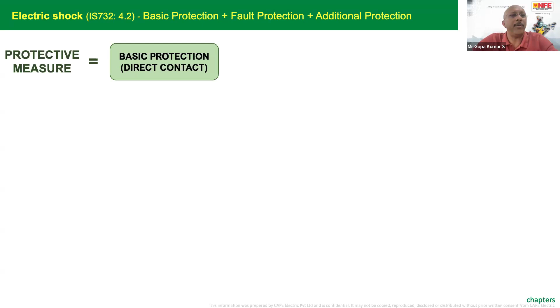If somebody claims that I have a product tested as per IS 732, I request the participants to be alert and careful, and immediately decide that this is wrong, because a product cannot be certified as per the requirements of IS 732. Clause 4.2 of IS 732 explains protection from electric shock, which consists of basic protection, meaning different protective measures which can be applied in an installation so that human beings or living beings do not come in touch with electricity. For example, insulation of live parts. Once we insulate, what kind of insulation, how much voltage the insulation has to withstand, how much distance, several technical parameters come into the picture. The second is barriers or enclosures, obstacles, and placing out of reach. These are the identified basic protective measures. Earlier, we used to call it protection against direct contact.